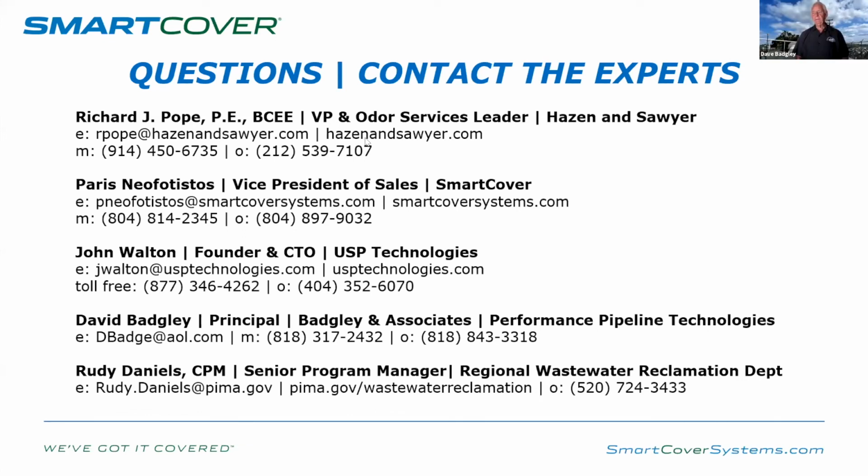This is Dave. Sorry. One of the other things that happens, kind of as a rule of thumb, where we have a force main discharge, usually I'll have deterioration in the next 5 manholes down. You don't want to just fix that one manhole. You want to keep looking on down the system to where it's deteriorated or vented enough that you don't have the higher concentrations of H2S.